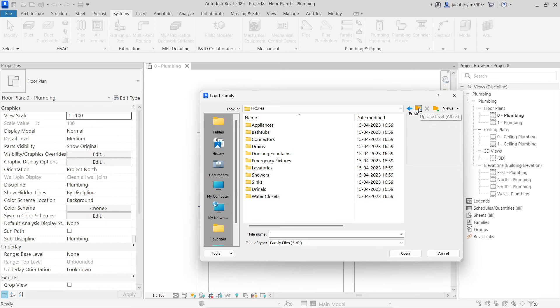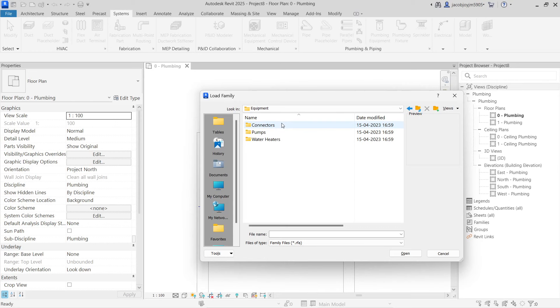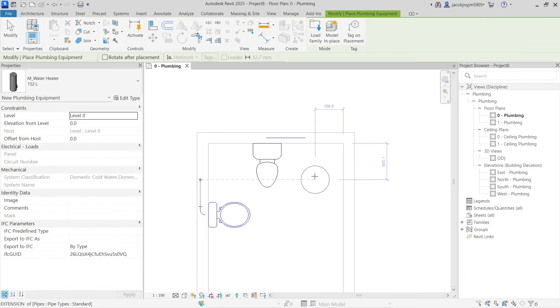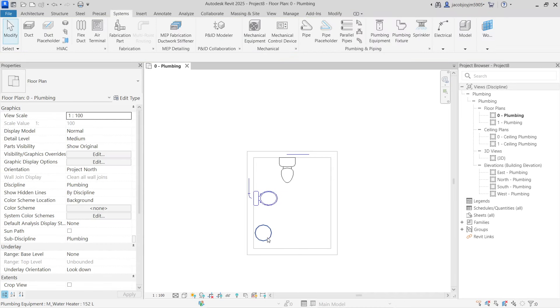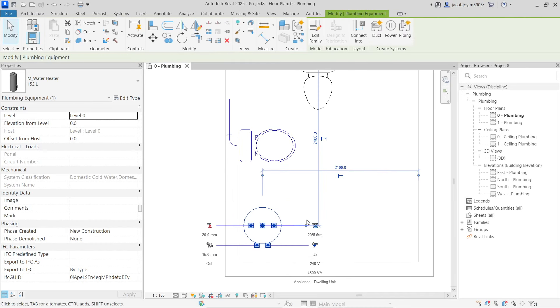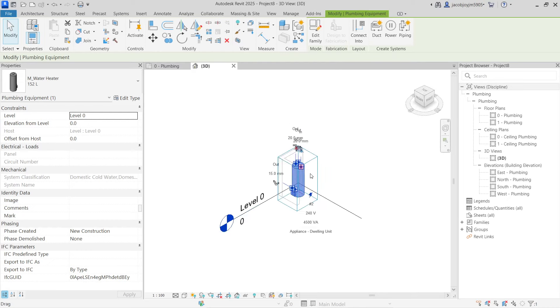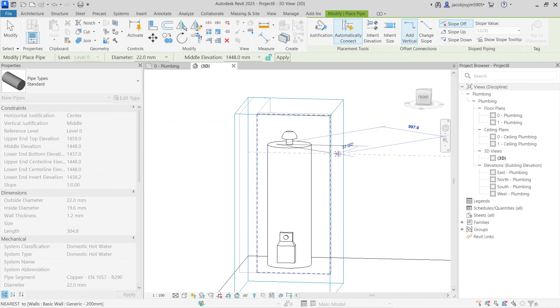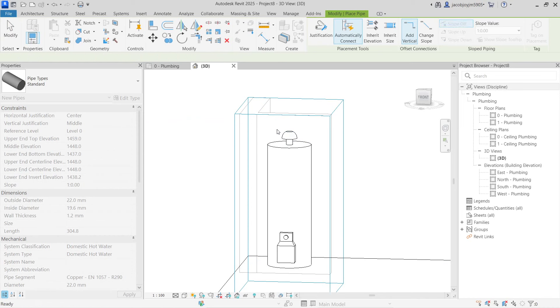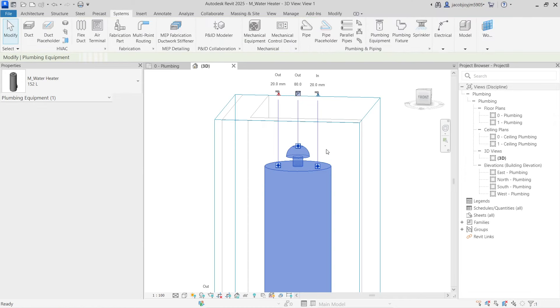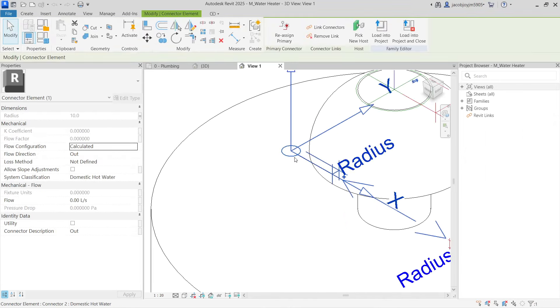In case you want to place plumbing equipment, for example a water heater, go to Equipment, select Water Heater, and place it. This water heater has all the connections so you can create pipes. The first pipe is supposed to be vertical. If I right-click and create a pipe, I cannot go horizontally first — I have to go vertically. This is because the pipe must go perpendicular to the placeholder connector.